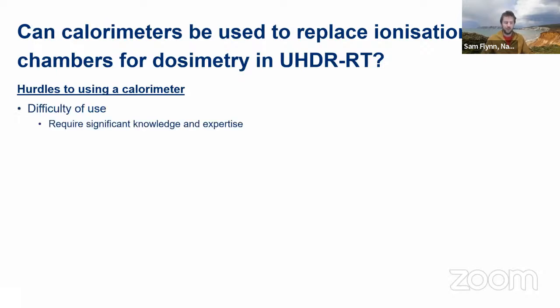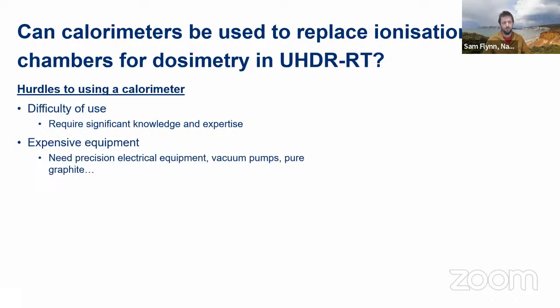You've got to have fitting expertise. You've got to understand the different heat mechanisms. They're not simple devices. They're really expensive as well. A good chamber might cost you a few £1,000s. My calibration, another several £1,000s. And the electrometer, a nice one, say £10,000. You're looking at a £20,000 total budget. But that might only get you the cost of one of the precision digital multimeters we're using for the calorimeter.